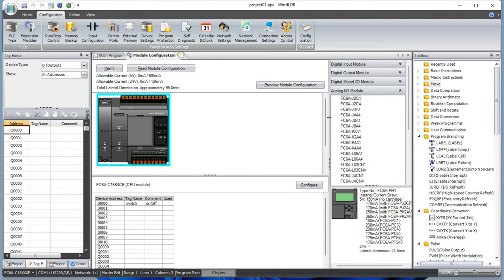The analog I/O module is used if you are measuring the temperature from a temperature sensor. It's continuous data, it's analog, not digital, just on and off like digital inputs and outputs. That's when you use an analog module connected to the sensor, or the pump pressure, those kinds of continuous data you grab, or the flow meter, where you grab the data in terms of voltage or 4 to 20 milliamps current, and convert that to the temperature in real, or floating point value.